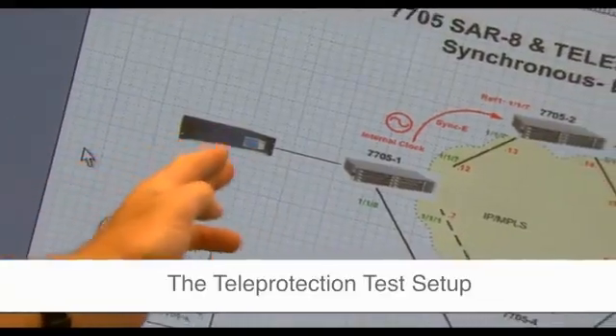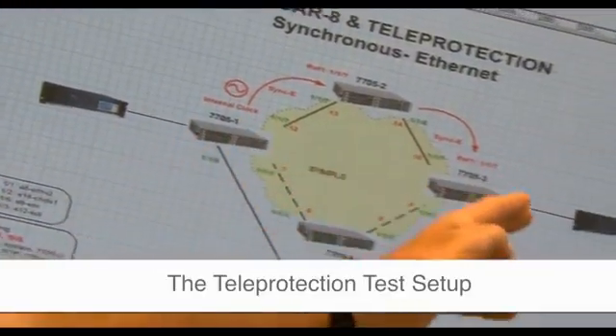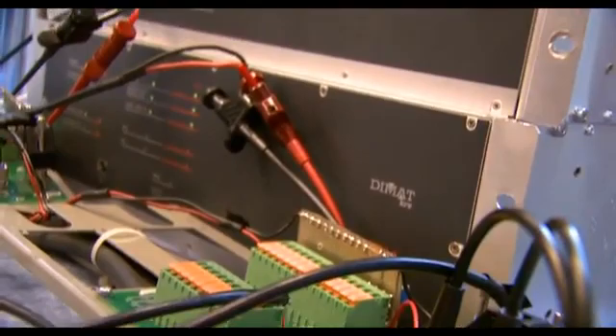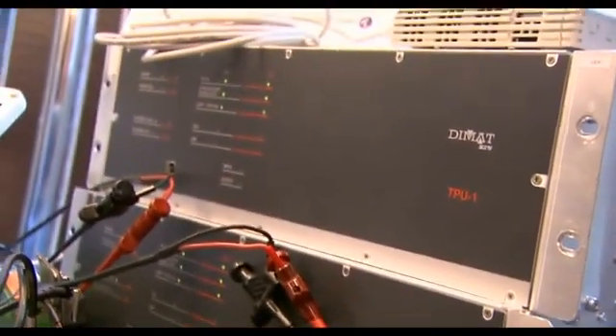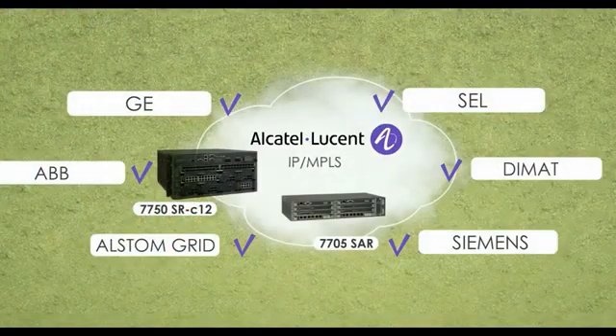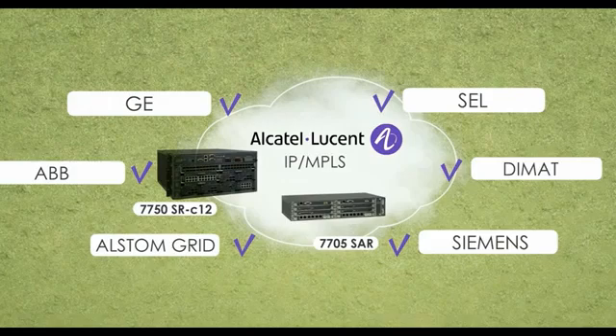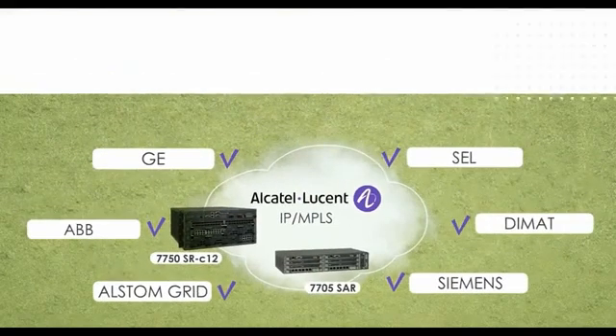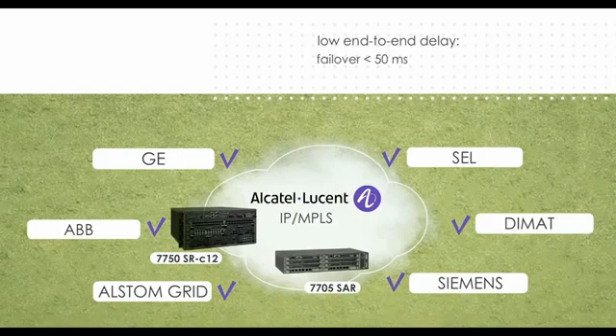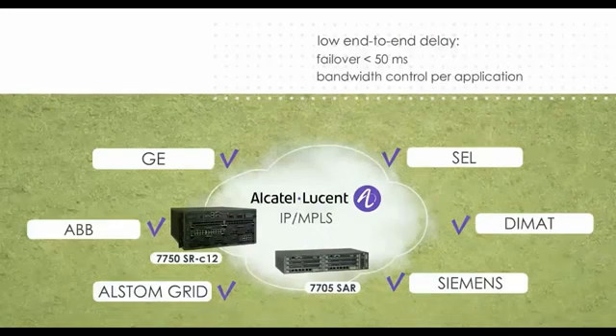Alcatel-Lucent and third-party laboratories have also conducted testing sponsored by utilities or relay manufacturers and evaluated teleprotection equipment from ABB, Alstom Grid, Siemens, ZIV-DIMAT, GE, and SEL connected to Alcatel-Lucent IP MPLS communications equipment. These tests again demonstrated that low end-to-end delay could be achieved, that failover capabilities met the sub-50ms standard for traffic rerouting, and that control of the bandwidth required per application was achieved with an Alcatel-Lucent IP MPLS network.